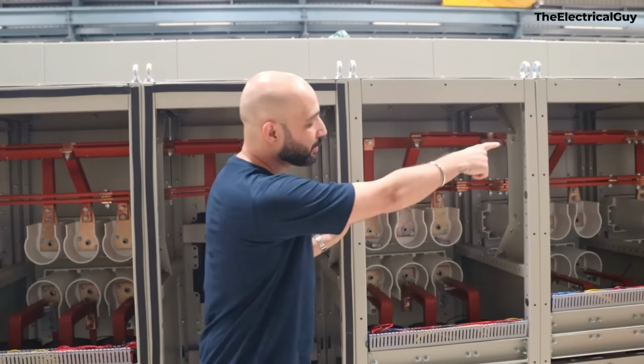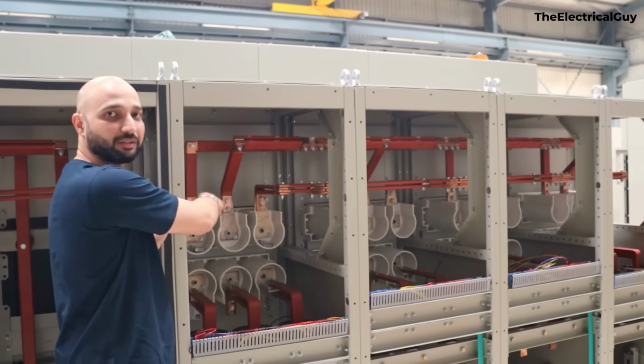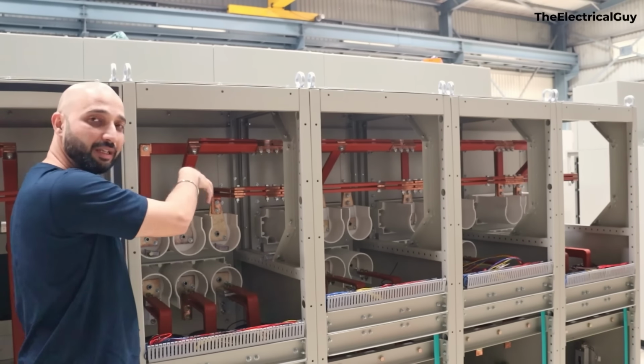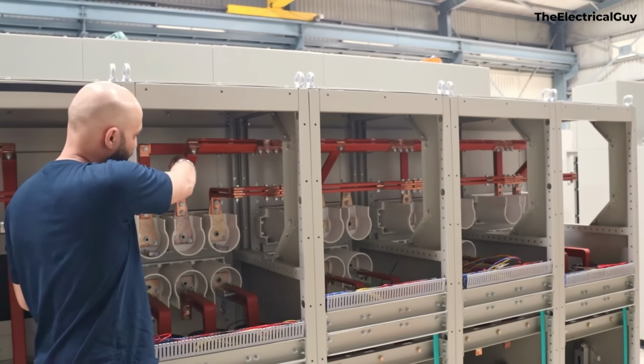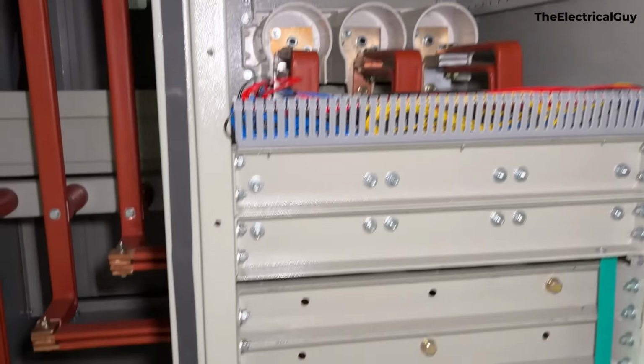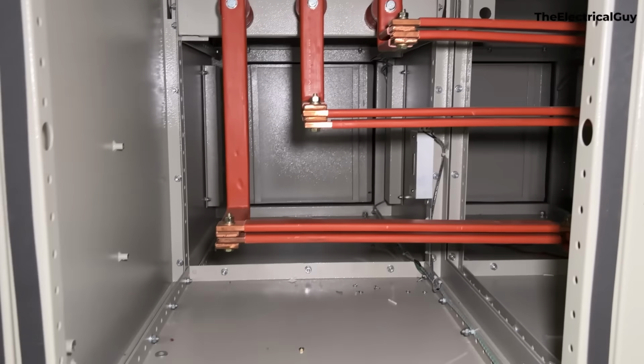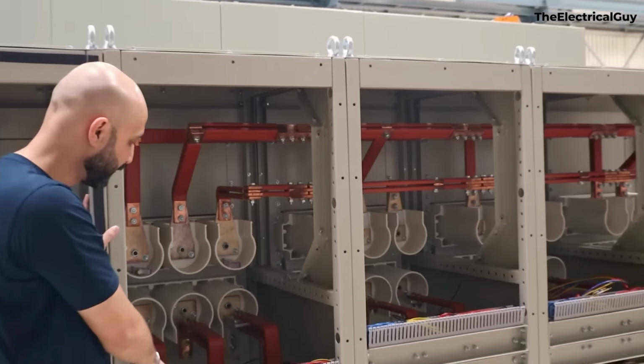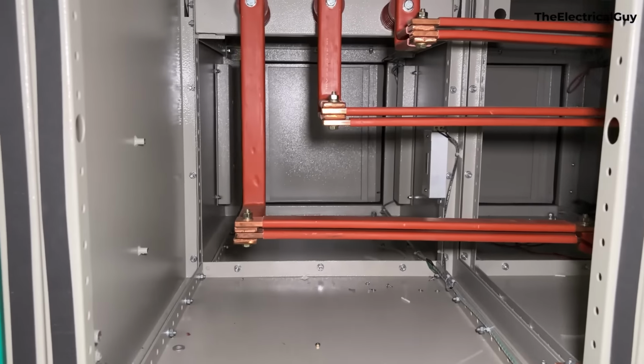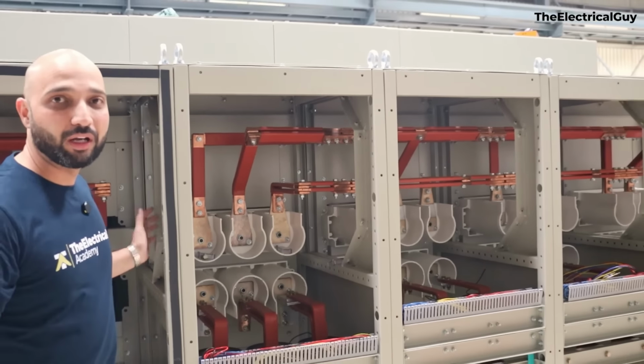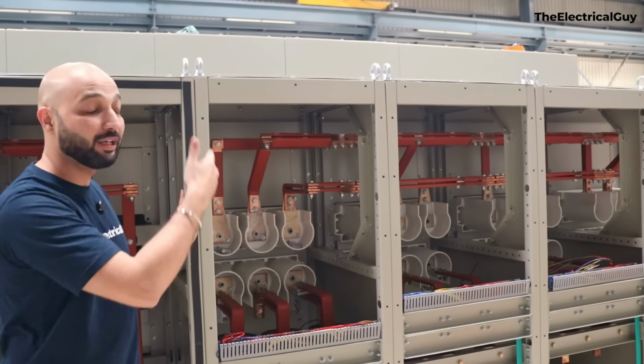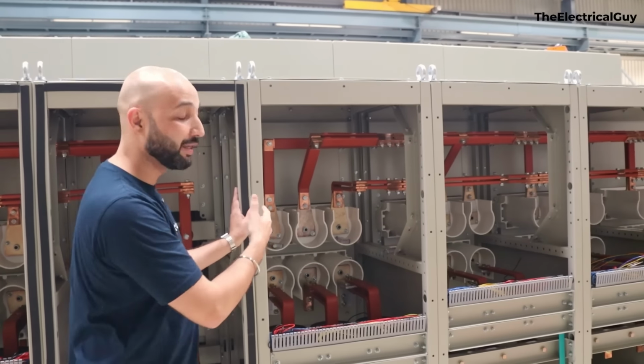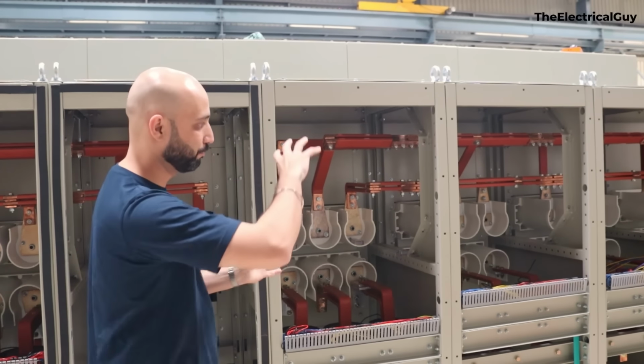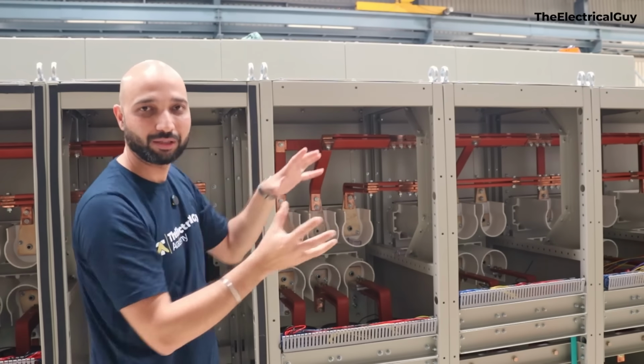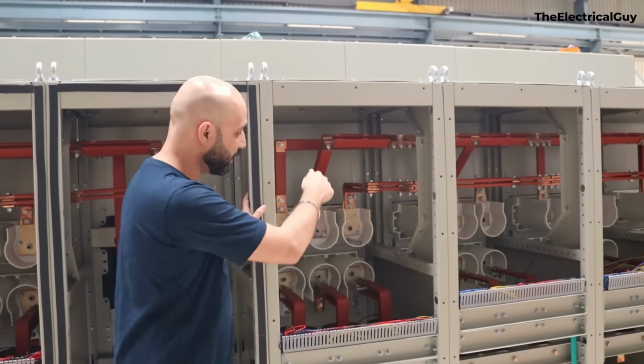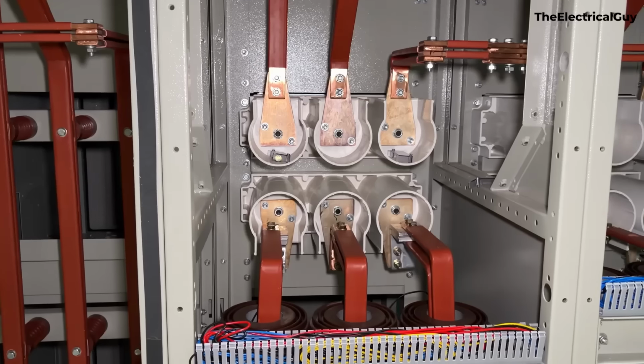So you can see the bus bars are coming that way. We have connected a circuit breaker here. It's a series connection, right? So we have incoming this for circuit breaker, and then the outgoing is coming out of the circuit breaker here. We have a current transformer placed, and then you see the bus bars are going down. Now these are going down because we have to connect it in vertical positions. That's how the breaker accepts the supply, right? We cannot rotate it and put it in that panel. That's not possible. And that's the reason why the bus bars are going down.